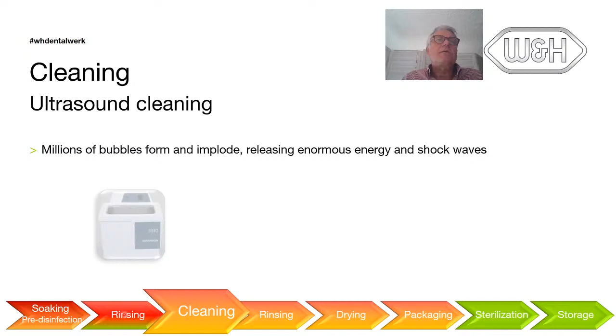It's an ultrasonic cleaner. So inside this chamber, we have a solution, this enzymatic solution, and below you have 2, 4, 6 transducers; the bigger the chamber is, the more transducers. And these transducers will create the noise. It's a terrible noise. It will create compression and decompression. Okay, try to move your hand in water. You can see small bubbles. So this is decompression. It will generate small bubbles which will implode.